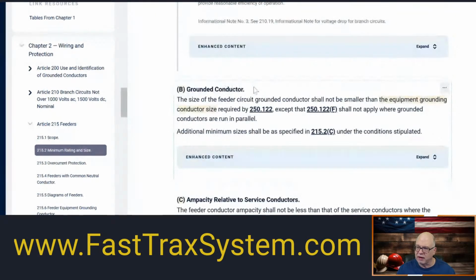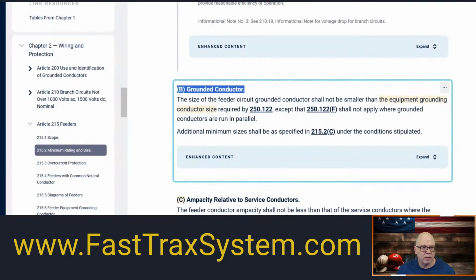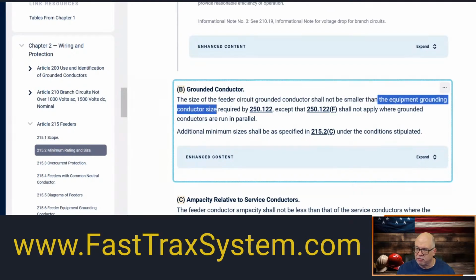And then you see right here, grounded conductor for a feeder. The size of the feeder's grounded conductor shall not be smaller than the equipment grounded conductor size required by 250.122, except in 250.122(F), that's dealing with parallel applications, okay, when you're running them in parallel, okay? Okay, so this one's easy.